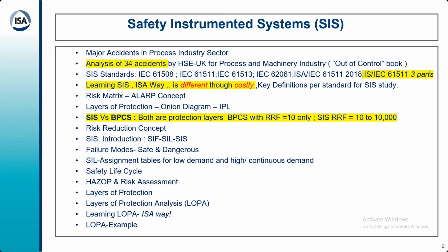Layer of protection analysis, we'll try to touch that topic. It's a semi-quantitative type of analysis compared to other types of risk analysis, which are qualitative in nature. In Europe, qualitative risk analysis is more prevalent, that is risk graph and risk matrix, whereas in America, it is LOPA which is more prevalent. And LOPA has advantages over the other types, so we will try to discuss that. And again, I will try to re-emphasize learning LOPA the ISA way, and we shall have a small example of LOPA so that people can understand that part of it.